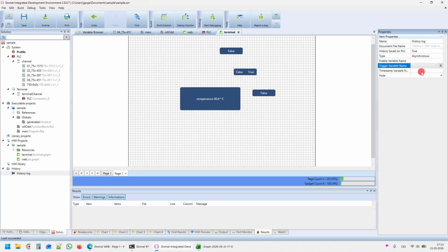The PLC can store 40,000 integers and they are overwritten starting from the oldest. So if, for example, I save one integer every minute, the history will last me a month. If every hour, then 2 years. It also depends on the data type of the variable. I will say more booleans than integers and less reals.